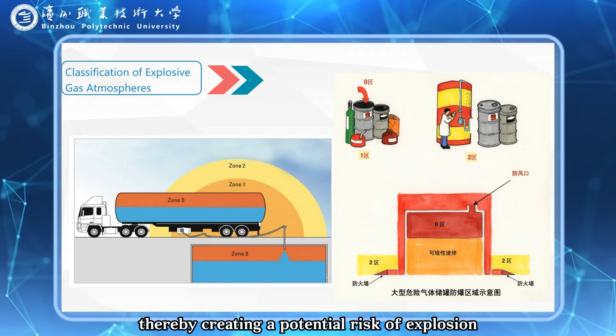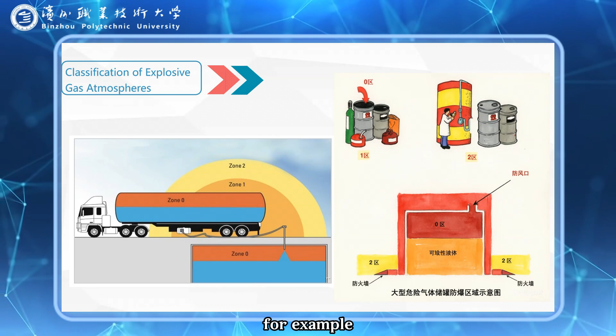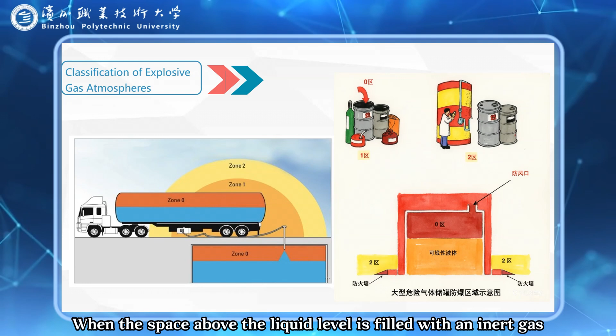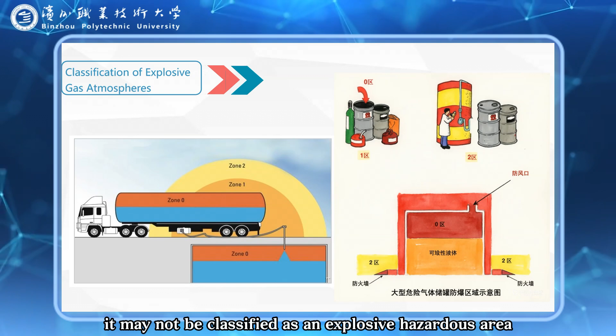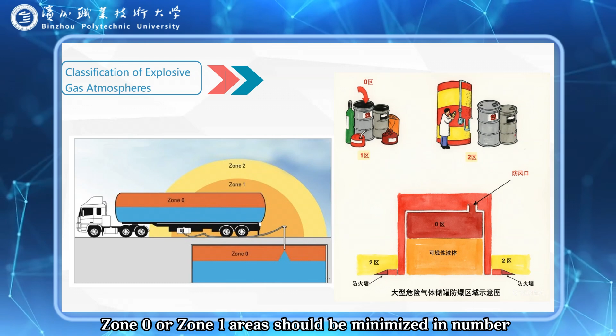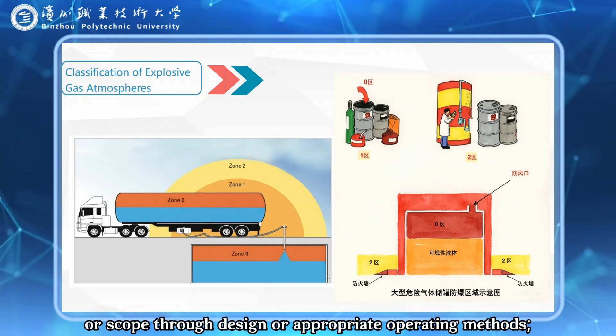Although mixtures above the upper explosive limit do not form an explosive atmosphere, environments where such mixtures could enter the air and reach the explosive limits should still be classified as Zone 0. For example, storage tanks for flammable substances with fixed roofs. When the space above the liquid level is filled with an inert gas, it may not be classified as an explosive hazardous area. During design, Zone 0 or Zone 1 areas should be minimized in number or scope through design or appropriate operating methods.